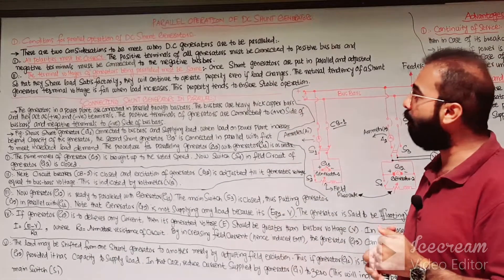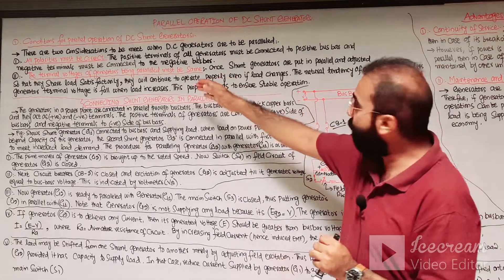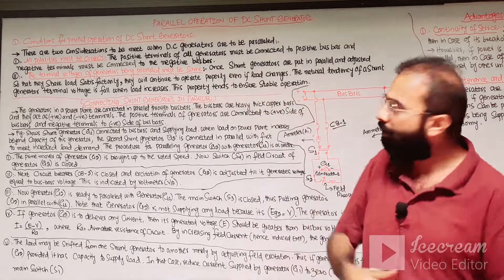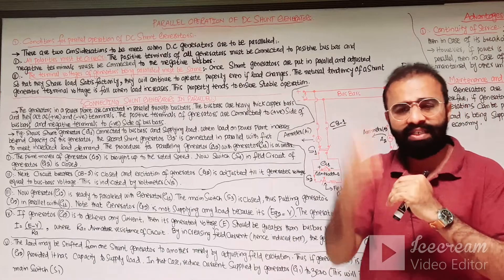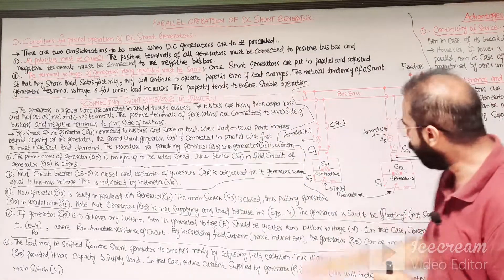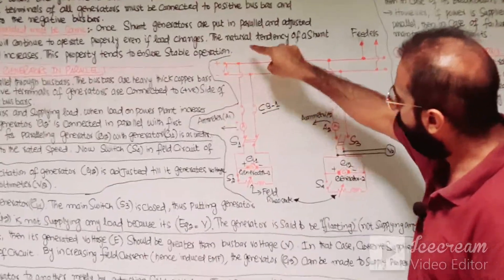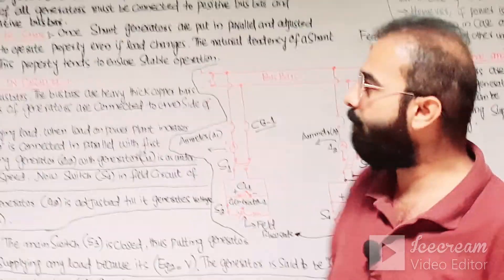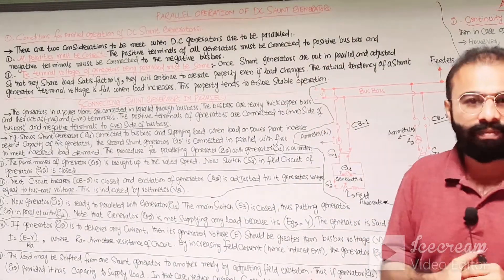Let us discuss the conditions for parallel operation of DC generators. There are two main essential considerations to be met when DC generators are to be connected in parallel. The first is that all polarities must be correct. The positive terminals of all generators must be connected with the positive terminals of the bus bar, and the negative terminal of the G1 generator is connected with the negative terminals of the bus bar.